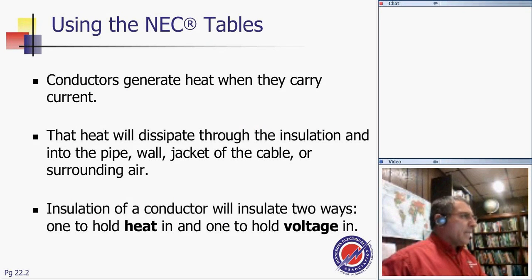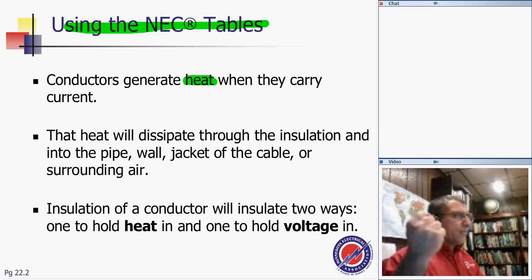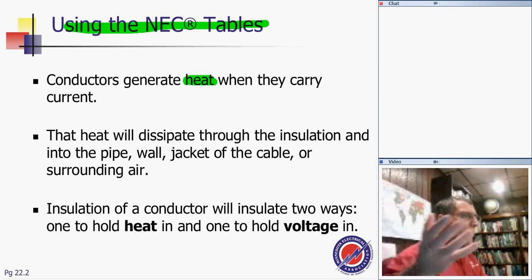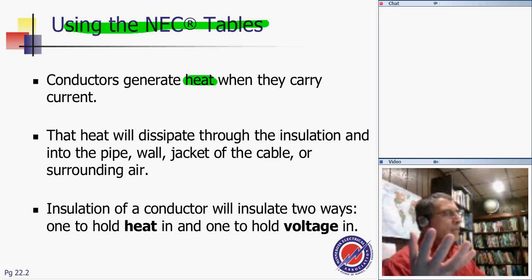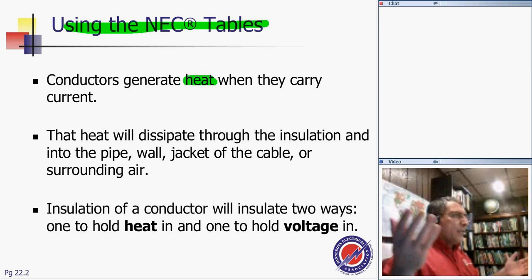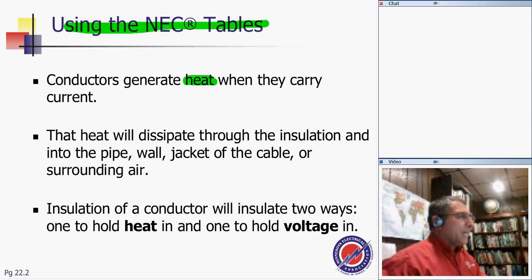The thing that's important, guys, when we size conductors, I'm going to share the NEC code book with you, and I highlight certain things I believe I've done in the past, but I'm going to do it one more time. The most important thing about a conductor current is heat. Every time you have a current going through a conductor, it generates heat. Who cares? Heat is enemy number one of electricity. Why? Because heat can deteriorate the insulation. Who cares? Then somebody sitting there says, who cares? Let the insulation deteriorate. Well, we care about smoke coming out of the conduit and short circuit, then melting all this insulation. And next, when you melt the insulation, you're going to have phase-to-phase short circuit, tripping a feeder or a branch circuit and losing the power. If you don't care about this one, then no problem about voltage drop and the whole ampacity tables.